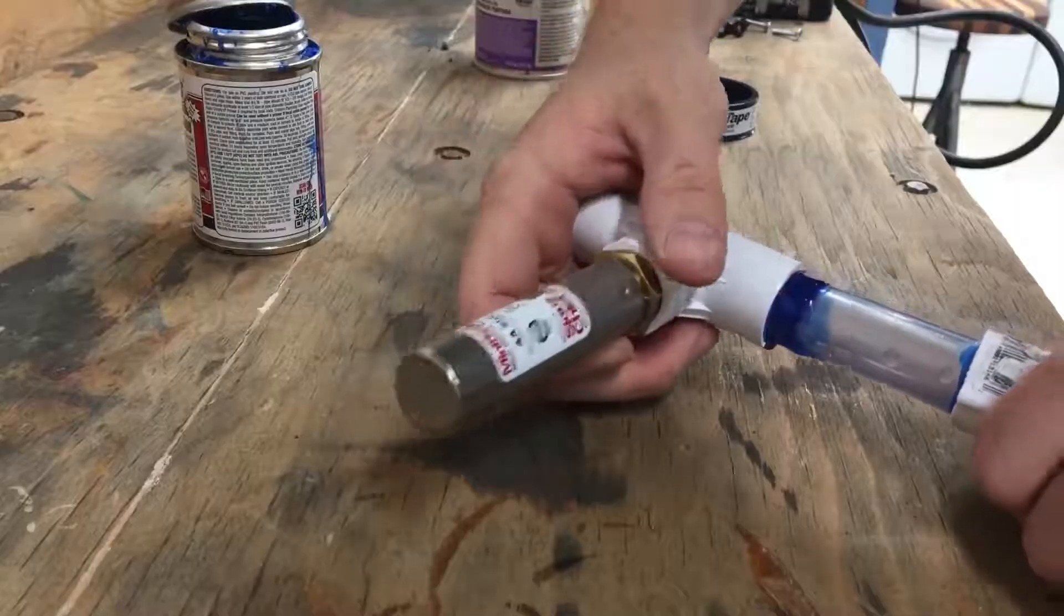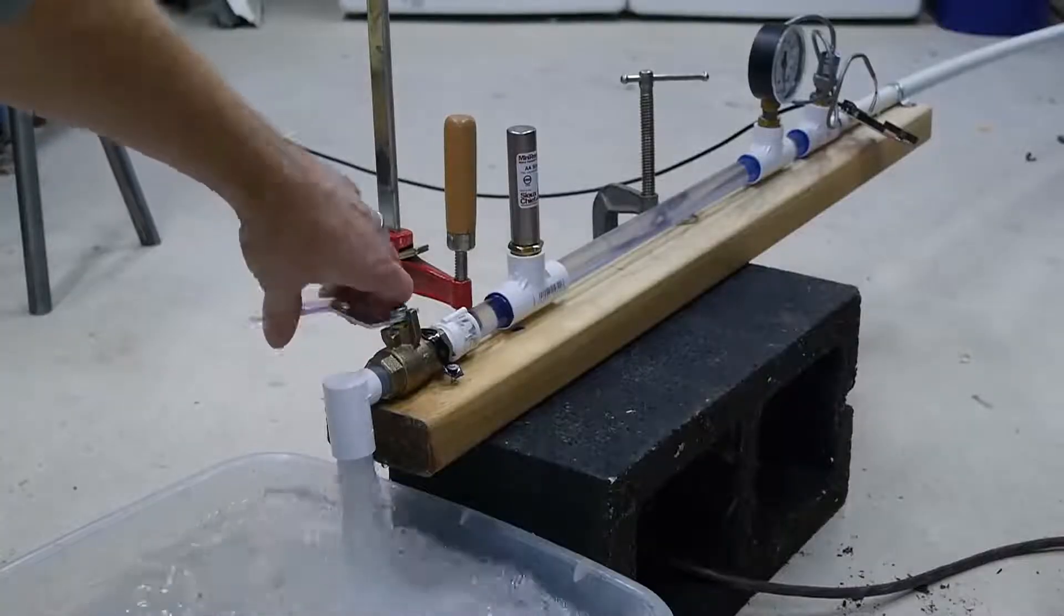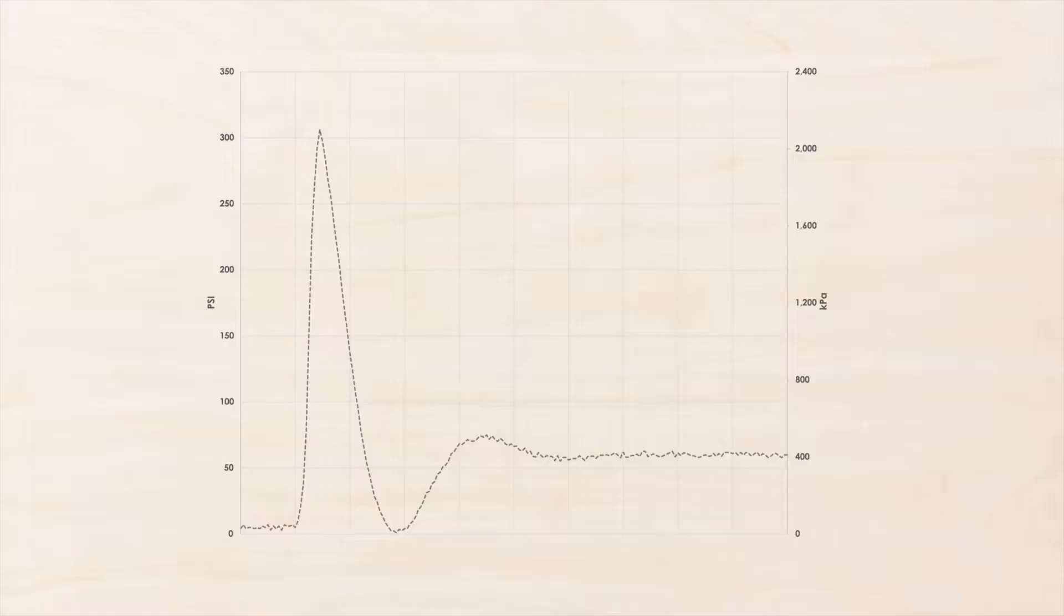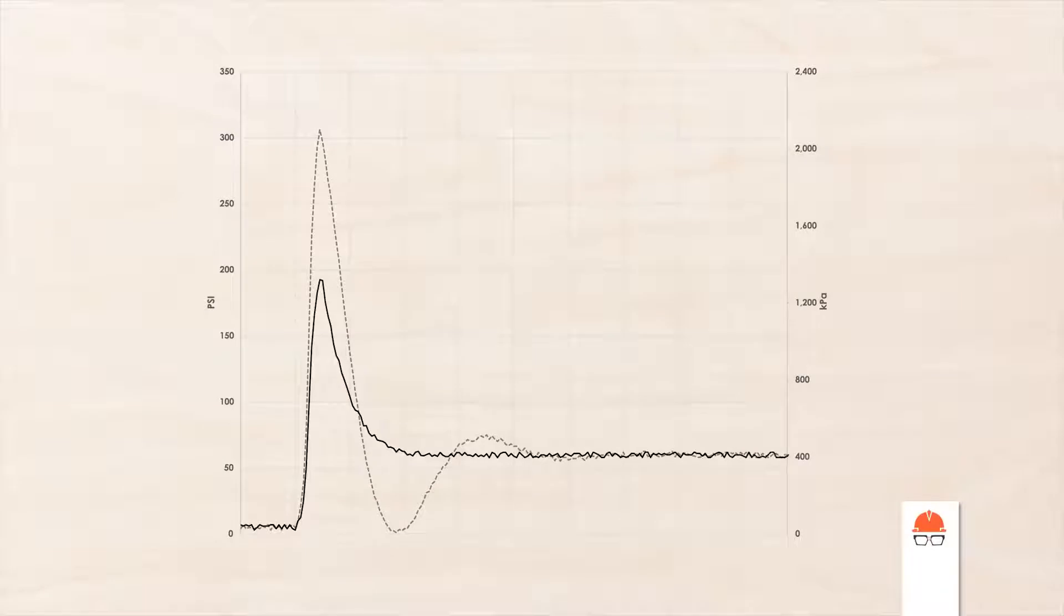I can increase the flexibility even more by adding an anti-surge device. This has an air bladder that can absorb some of the shock and reduce the pressure spike even further. Anti-surge devices are very common in pipe systems, and they can be as simple as spring-loaded valves that open up if the pressure gets too high.